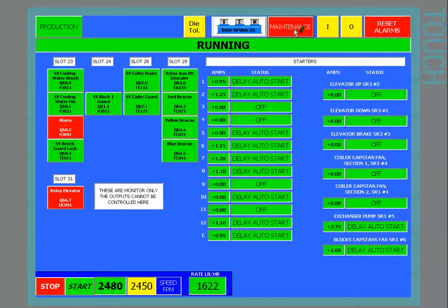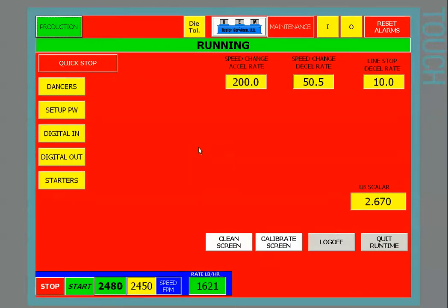We have a maintenance screen, and in the maintenance screen we will be able to gain access by entering a username and password, and hit the button again, and we're into the maintenance page. Here you can set the accel decel rates for the machine. When you make a speed change, your accel rate in this case is 200 seconds from 0 to full speed. The decel rate's 50.5 seconds.